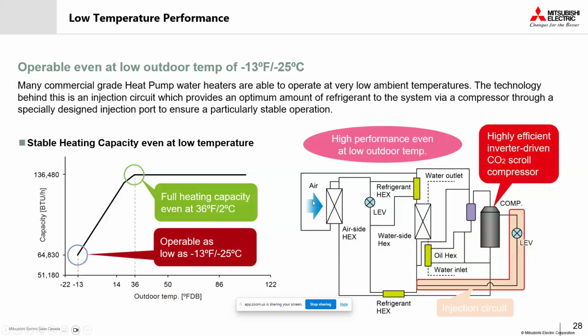So just looking quickly at the topic of low temperature performance, I'm sure a lot of the common misunderstandings are still out there. Even in 2025, there still can be some fear about using heat pumps in cold climates. But I would like to highlight the fact that most modern systems have overcome these challenges. Many commercial grade heat pump water heaters now perform very well at very low outdoor temperatures, thanks to technology like the flash injection circuit that we see here.